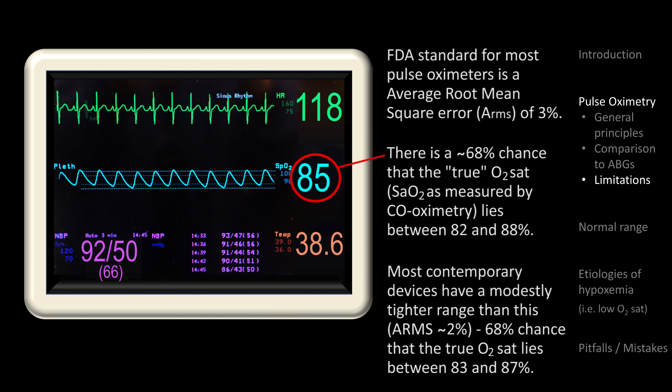Part of this error is systematic bias in one direction, which tends to remain relatively stable in a given patient, such that using the pulse oximeter to follow short-term trends in oxygenation will lead to more sound management decisions compared to making decisions based on a one-time value considered in isolation.